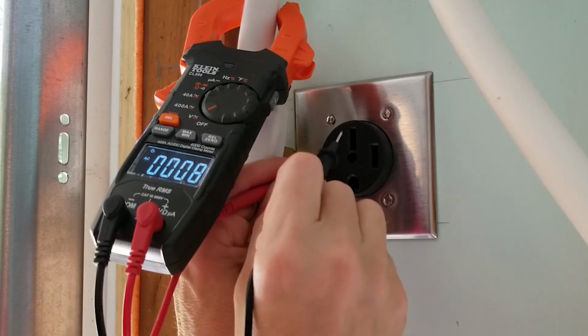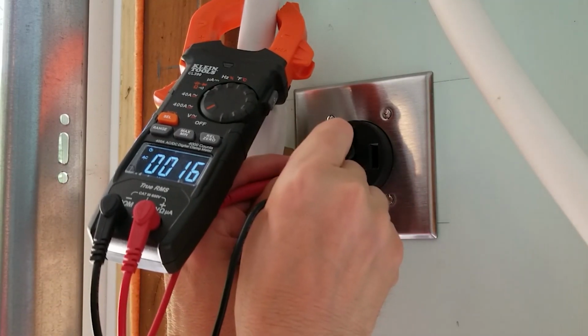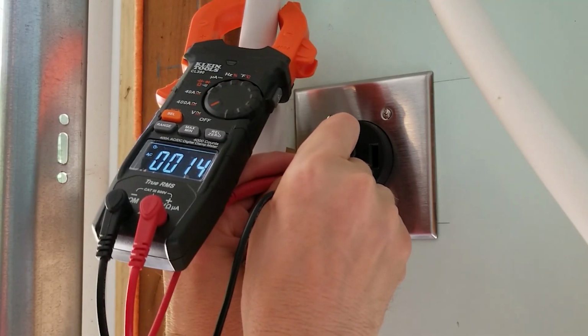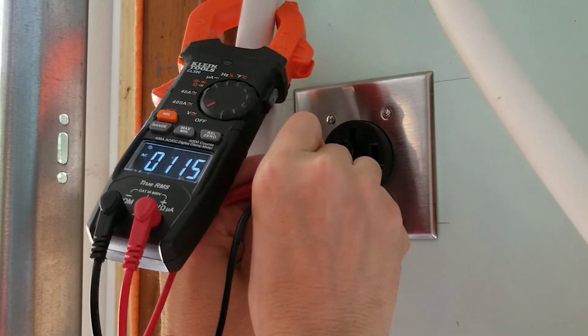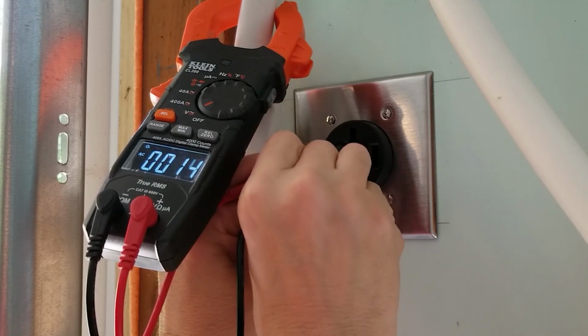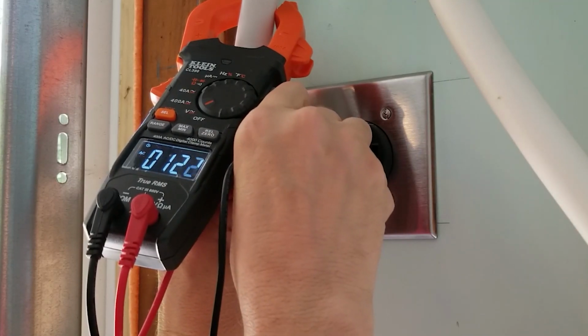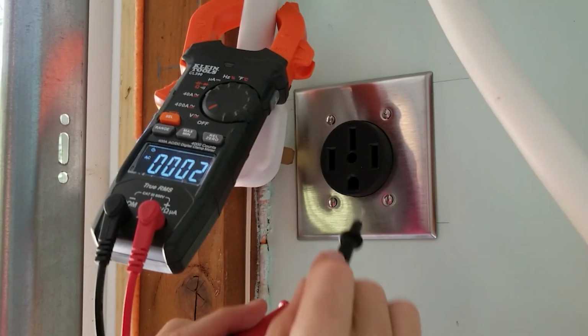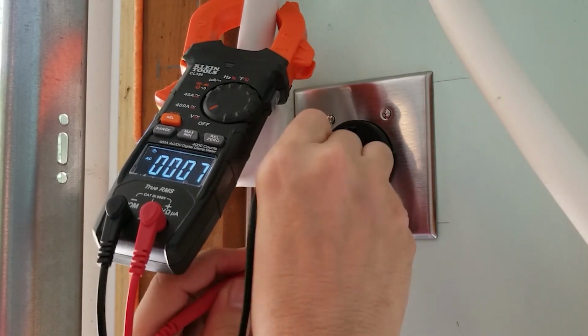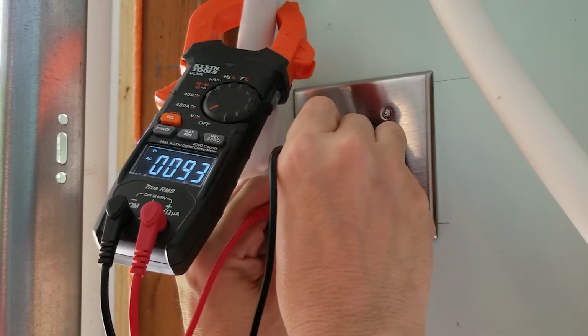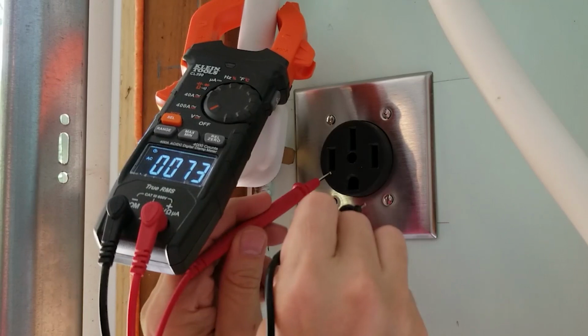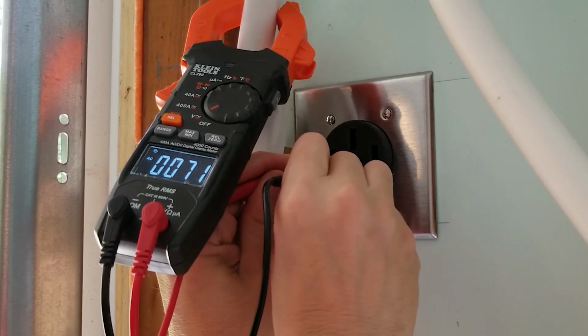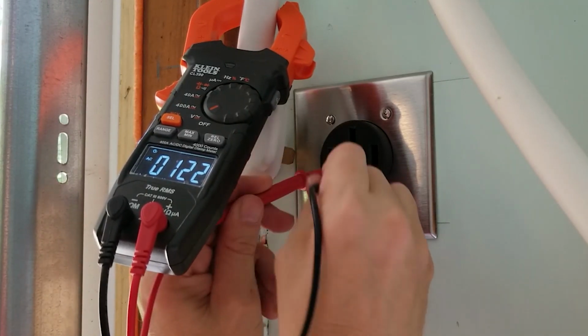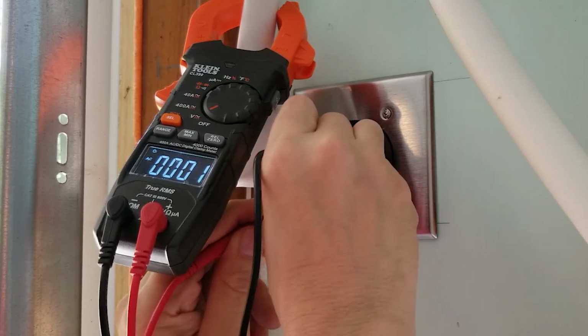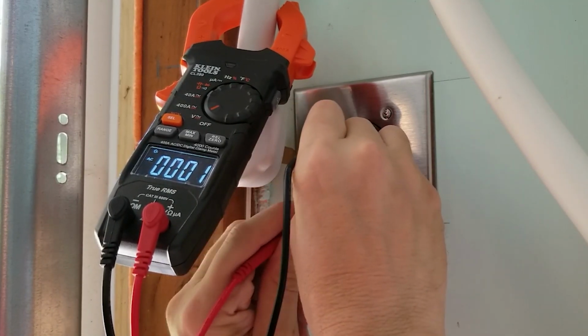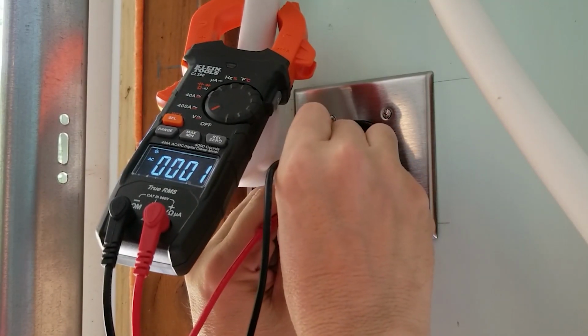And if we go from the other hot to the neutral, we should also get—once I make proper contact—122. And then from hot to ground, 122, 122, and from neutral to ground, there should be nothing.